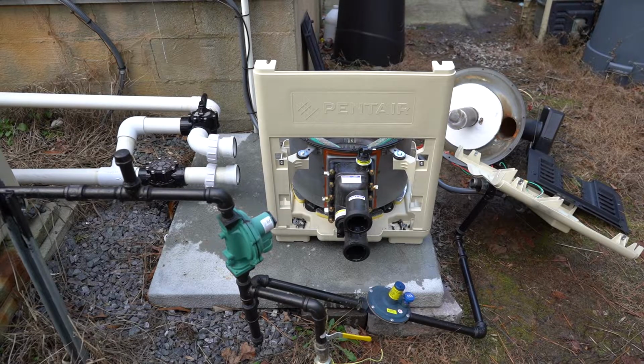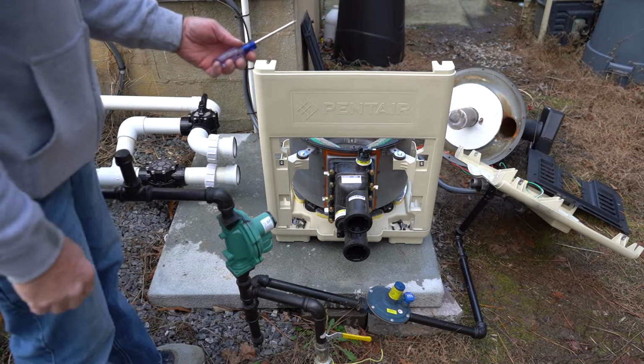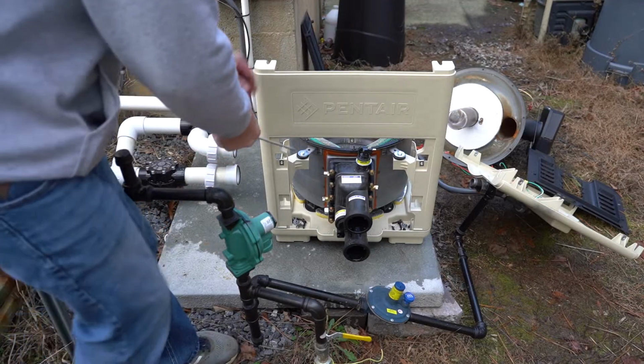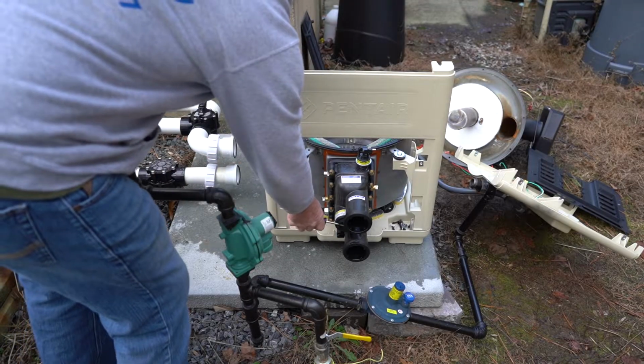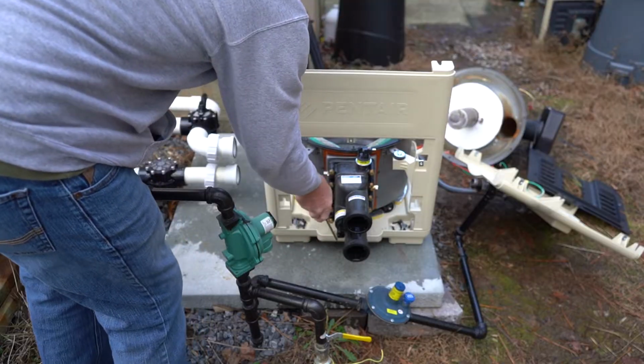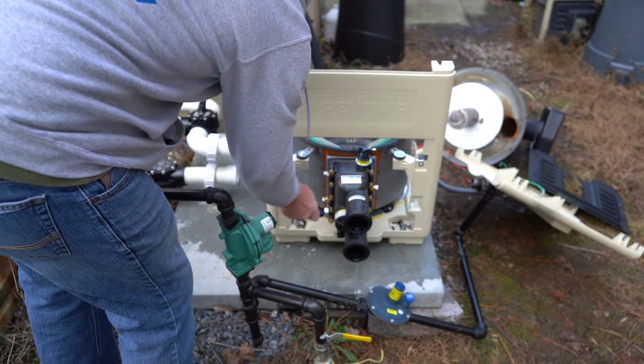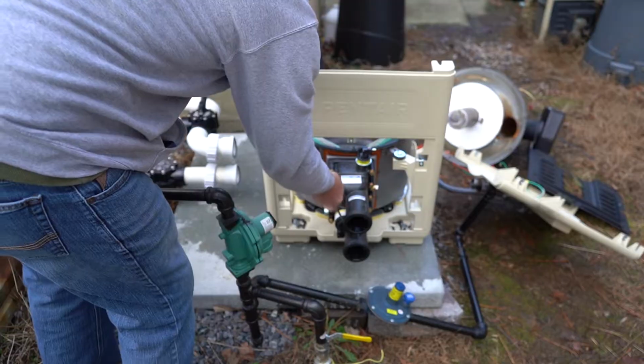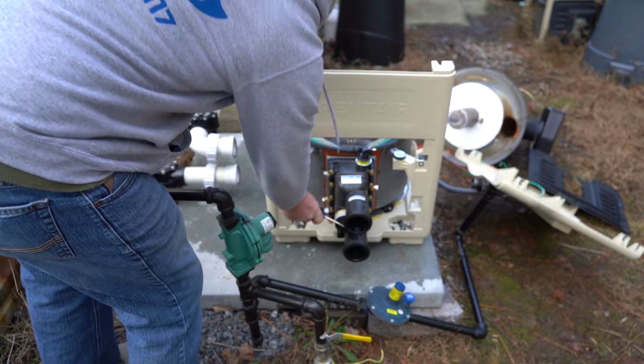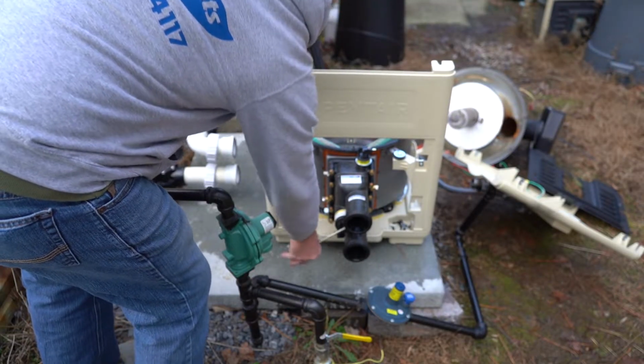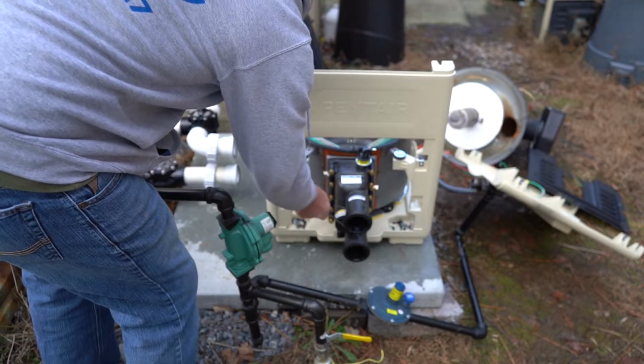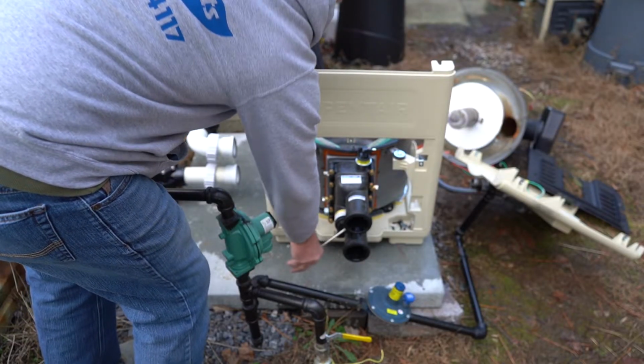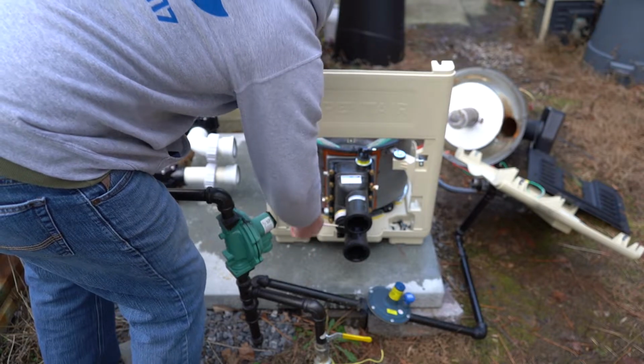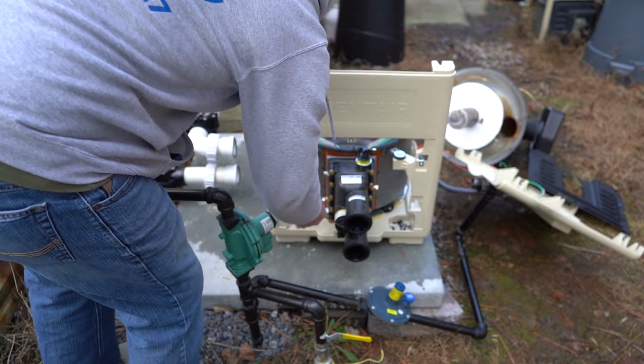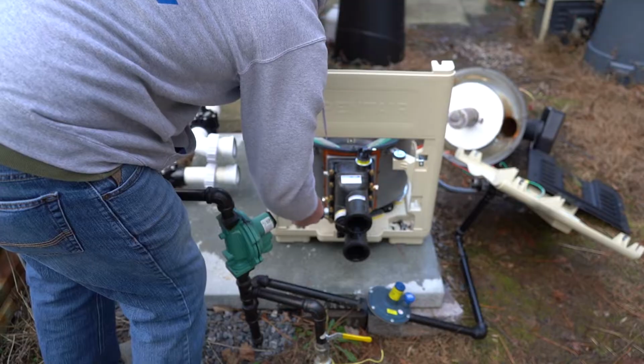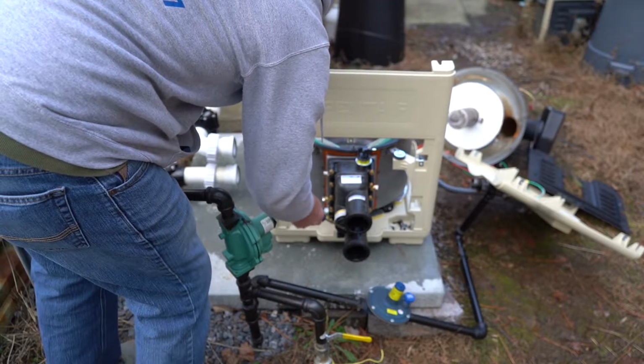To remove the thermal regulator, get yourself just a regular number 2 Phillips head, and put it in the castle nut, and just unscrew it. There's quite a bit of tension here because there's a spring that holds that thermal regulator in. I like to remove this so that when I take the manifold off, I don't have the issues of the pressure of that spring.